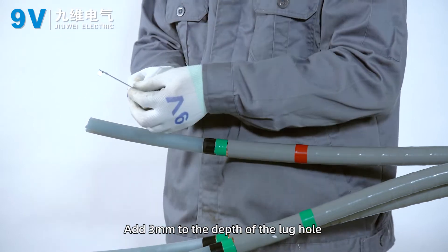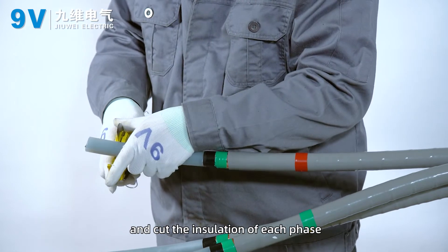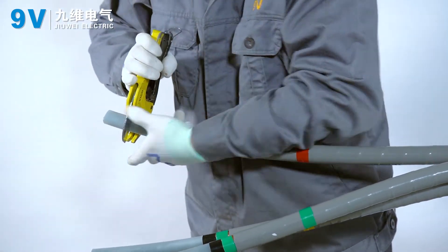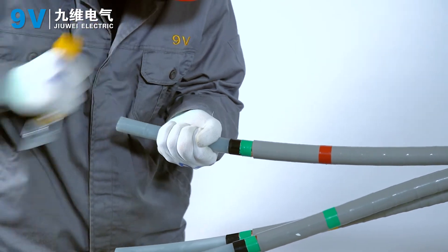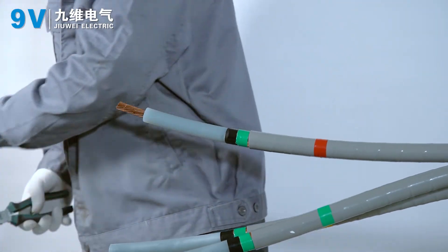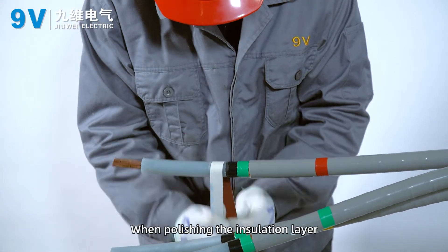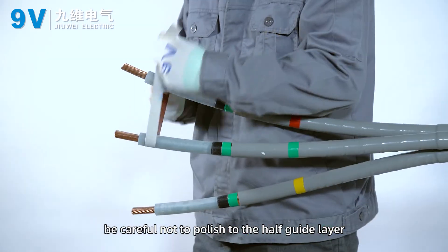Add 3 mm to the depth of the lug hole and cut the insulation of each phase. Sand the surface of the insulation layer with fine sandpaper, being careful not to polish into the semi-conductive layer.